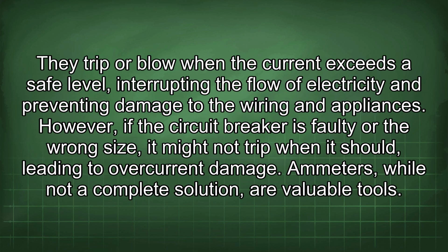Circuit breakers and fuses are designed to protect against overcurrent. They trip or blow when the current exceeds a safe level, interrupting the flow of electricity and preventing damage to the wiring and appliances. However, if the circuit breaker is faulty or the wrong size, it might not trip when it should, leading to overcurrent damage.